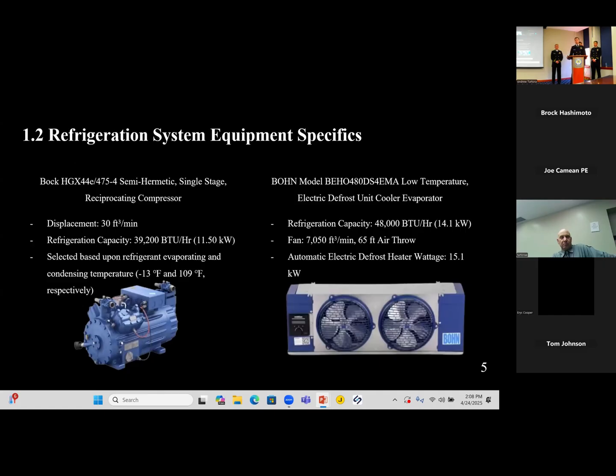In terms of equipment specifics, one of the major components is the Bock semi-hermetic single-stage reciprocating compressor. This has a displacement of 30 cubic feet per minute, a refrigerant capacity of 39,200 BTUs per hour, and was selected based upon our evaporating and condensing temperatures of -13 degrees Fahrenheit and 109 degrees Fahrenheit, respectively.